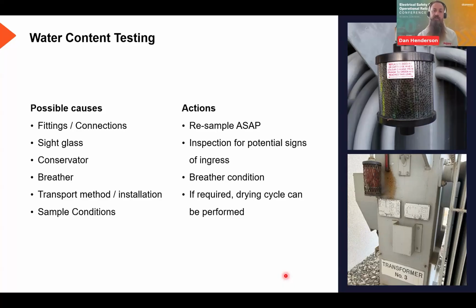So often the action is to resample as soon as possible. And often on that initial resample, it comes down to the sample conditions. So it might be raining at the time, it's such a common thing, or the actual sample equipment has been contaminated by water somehow, possibly by weather, possibly by storage, but often that is a key thing that happens.